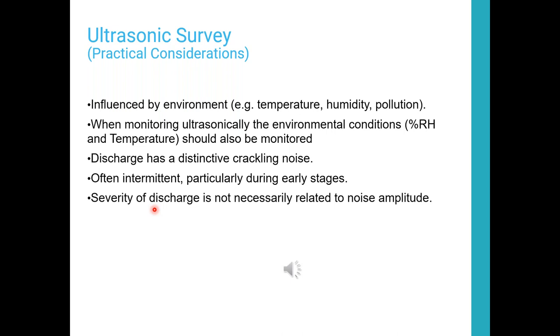And when we installed the full-time monitoring, it monitors 24/7. My engineers came back and said, hey, we've got to do something immediately here. This is very high levels of surface discharge. And I went back to the facility and said, this is our mains coming in. We can't shut down. We can't de-energize the facility. It takes us a week to get back online by the time we clean out all of our stuff in process and all that. So this can't happen.